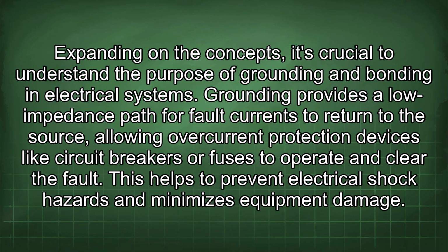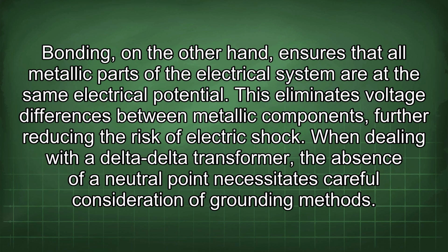Expanding on the concepts, it's crucial to understand the purpose of grounding and bonding in electrical systems. Grounding provides a low impedance path for fault currents to return to the source, allowing overcurrent protection devices like circuit breakers or fuses to operate and clear the fault. This helps to prevent electrical shock hazards and minimizes equipment damage. Bonding, on the other hand, ensures that all metallic parts of the electrical system are at the same electrical potential. This eliminates voltage differences between metallic components, further reducing the risk of electric shock.